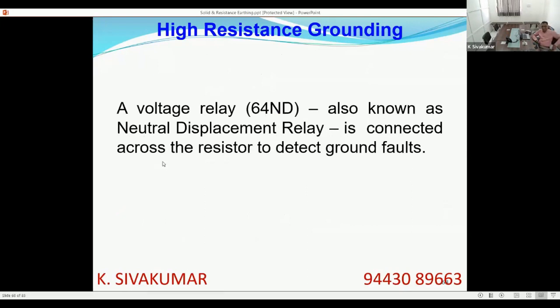Also, since you have a resistor and current is flowing, you will have a voltage drop. There will be a voltage across this secondary only when there is a current flow in the primary of the NGT, and there will be primary current flow in the NGT only when there is a system earth fault. So you connect a voltage relay, 64 ND or neutral displacement relay, across the resistor. Whenever there is a fault, current will flow in the primary of the NGT. It will set up a flux, the secondary winding will cut that flux and an EMF is induced in the secondary. This EMF is detected by the 64 ND and you can allow tripping of the system.